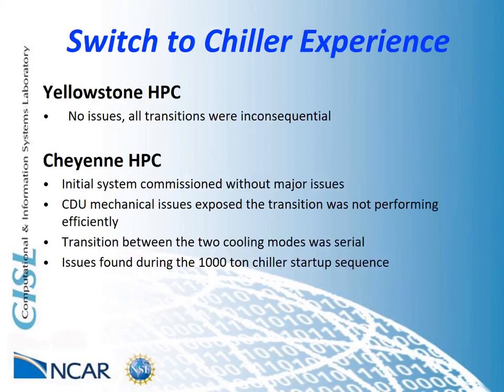Throughout the operation of the Yellowstone HPC system, the NWC plant experienced no major issues during all manual transitions between the free and mechanical cooling systems that were performed. As Cheyenne was being commissioned, all initial transitions between free and mechanical cooling showed no sign of major issues. However, as the HPC system aged, a few problems arose within the CDU subloop, where equipment inside the racks was getting dangerously close to their upper limit operating temperature ratings.